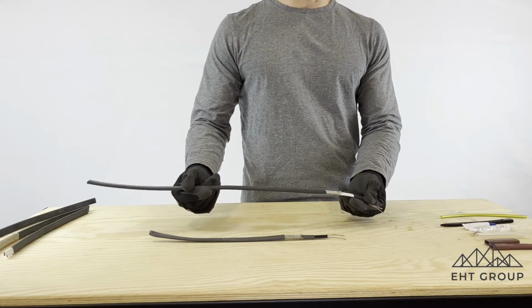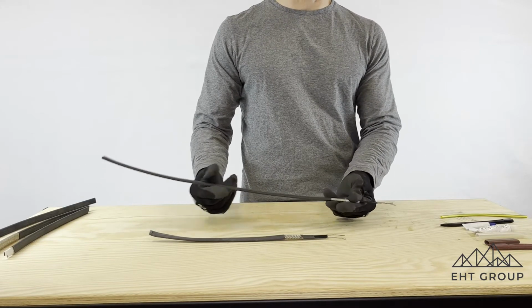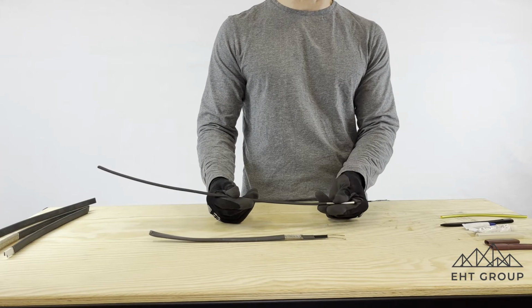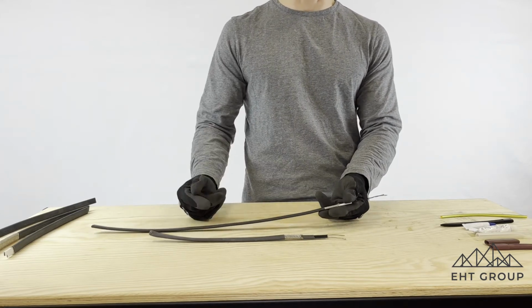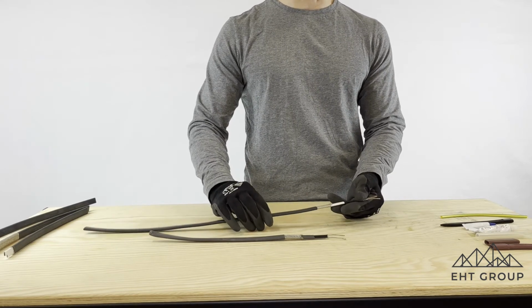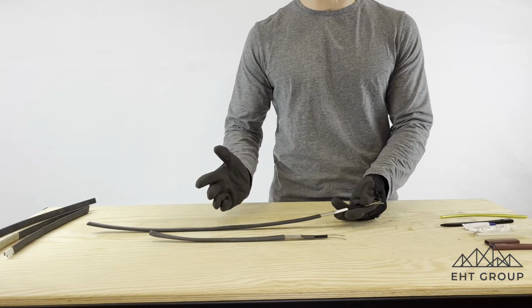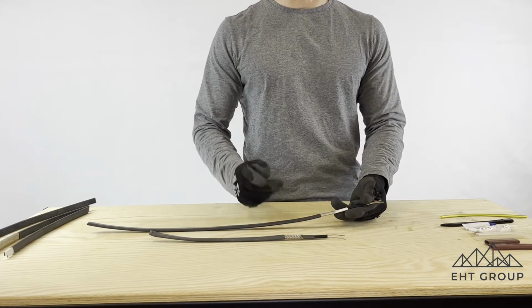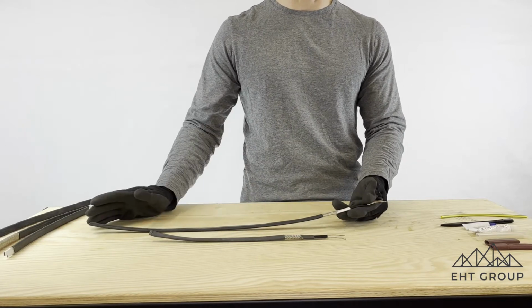So the next piece I want to talk about is some general power termination components and considerations for when you're doing terminations on an SR cable, or power terminations or end terminations. And the biggest failure point that we see with SR cable in the field is obviously if there's physical damage that's happened to the SR cable, but typically failures will happen at a power termination or an end termination point.